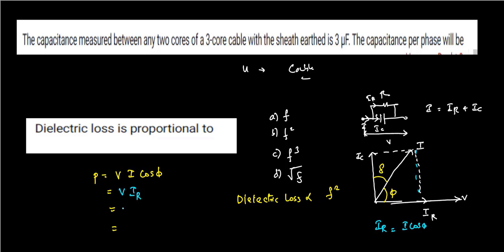But I want the dielectric loss. Dielectric loss depends upon this angle delta. The angle between IC and I is delta, and that represents the dielectric loss. What is tan delta here? Tan delta equal to IR by IC, sin by cos. So IR equal to IC into tan delta, and the power is V into IC tan delta.